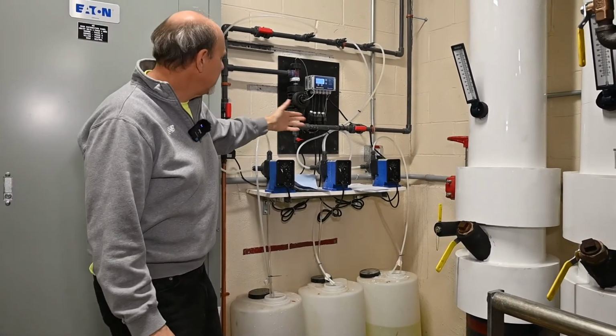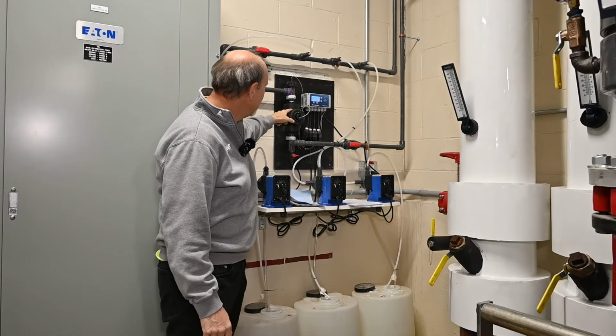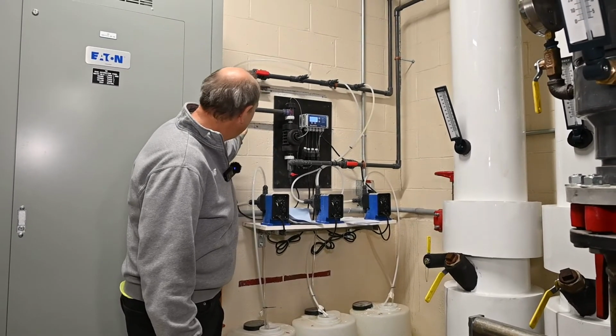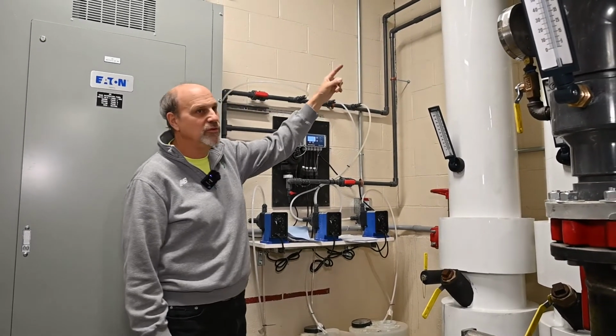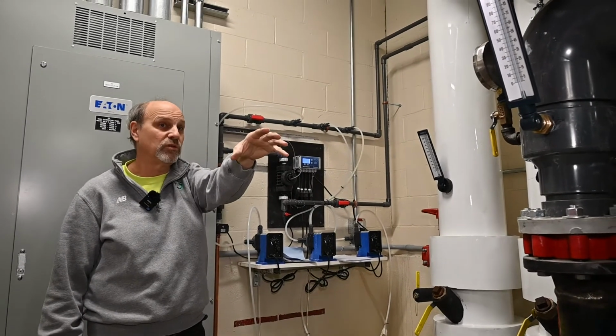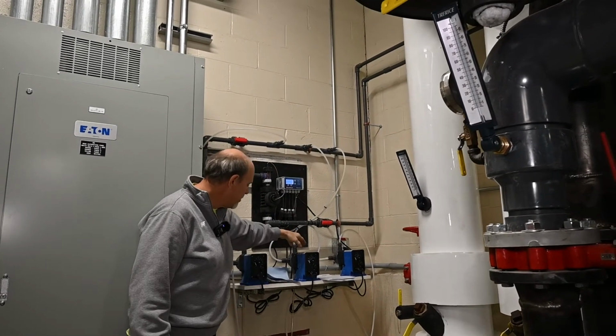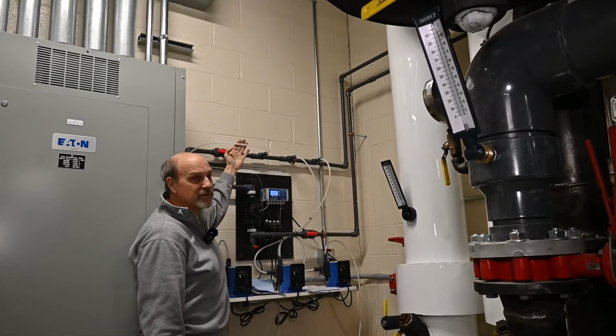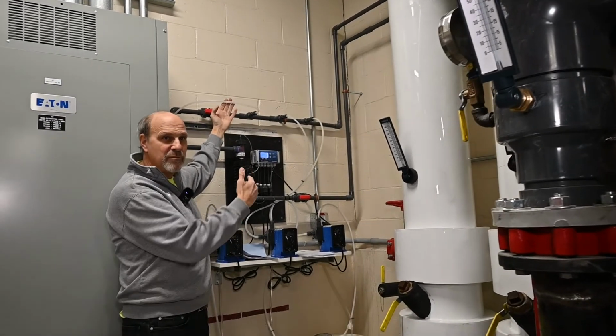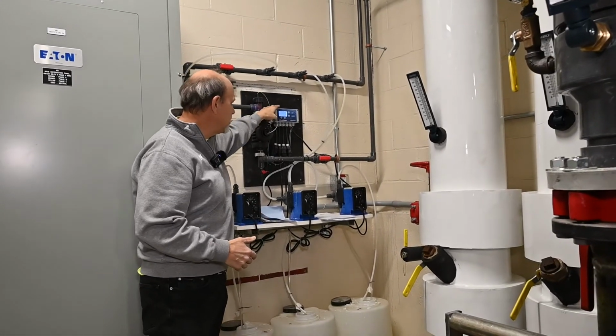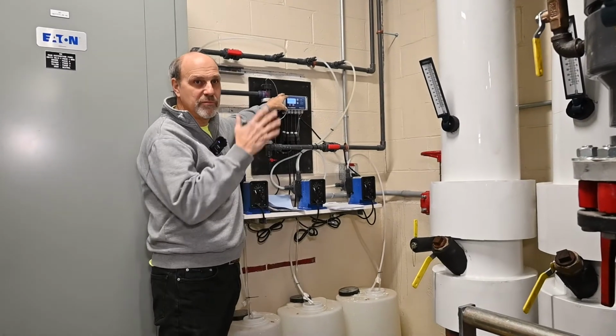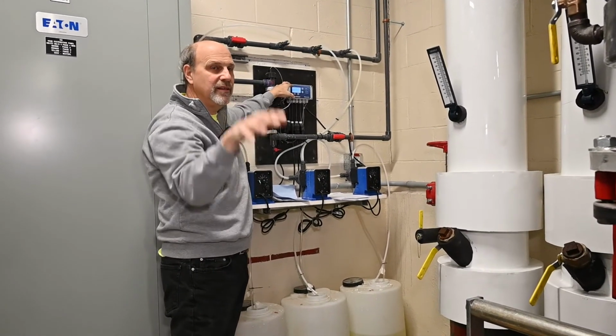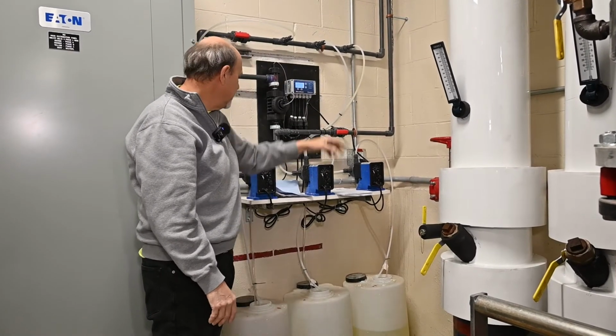Flow of water basically comes in through a conductivity controller and switch, and it just flows right back to the sump holding tank. But you've got a separate pump for 3 different chemicals with these injection taps in here. So that's how we admit chemical to the system based on this conductivity controller and what we should be maintaining for conductivity in the cooling tower system.